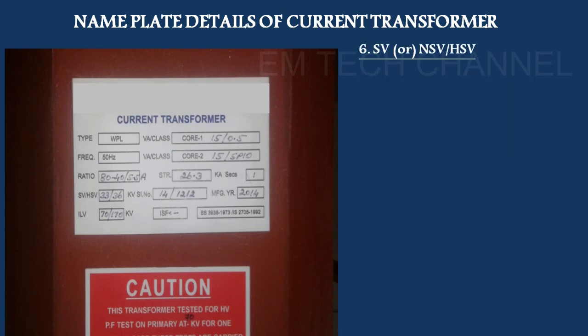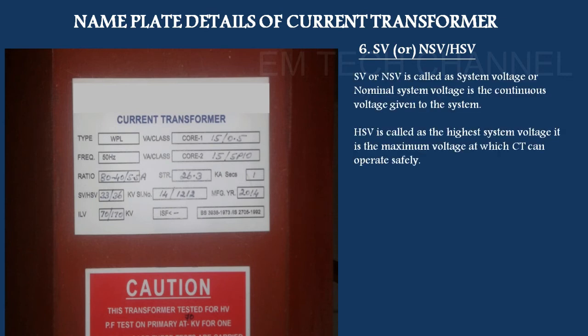SV is the system voltage. The nameplate will give the SV value. For example, 33 kV — the system is a 33 kV system. The CT is marked as 36 kV highest system voltage (HSV), which means the system normal voltage is 33 kV but the maximum continuous voltage it can withstand is 36 kV.